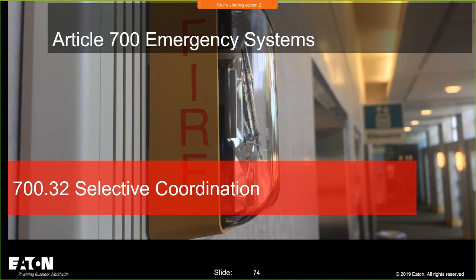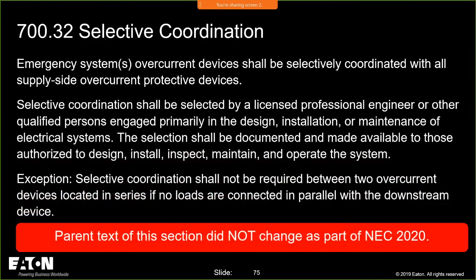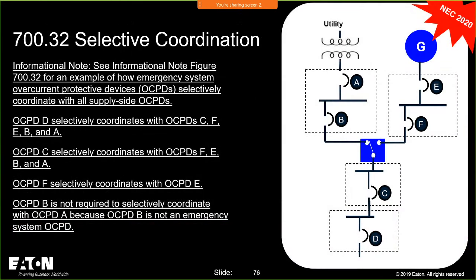Now, here's what we did in 700.32. The parent text of 700.32 did not change. You still have the same language that we just saw: licensed professional engineer or other qualified person, which we just saw in 645. And then there's the exception, not required between 2. None of that changed. But what they did was they settled the long-lasting debate, in my opinion, of what has to selectively coordinate in the system.